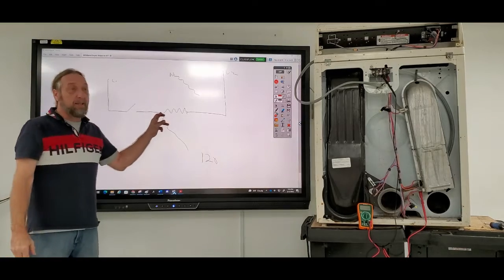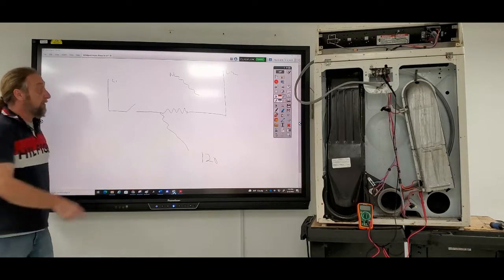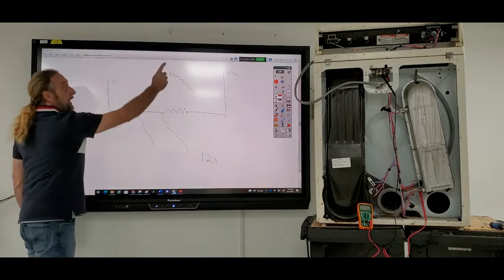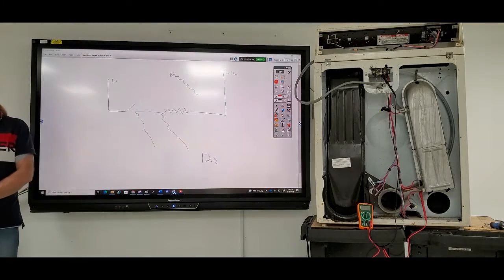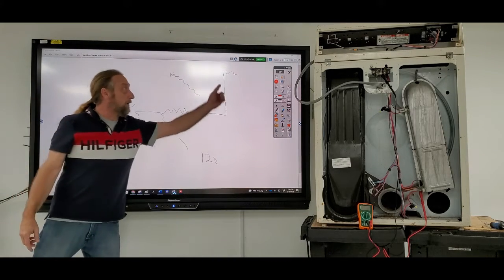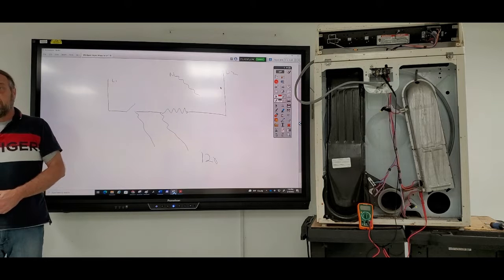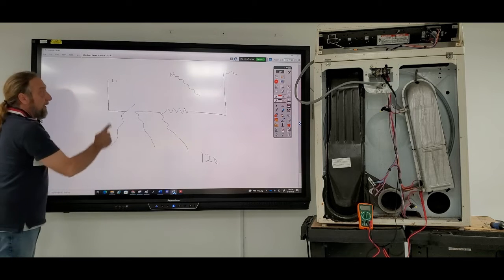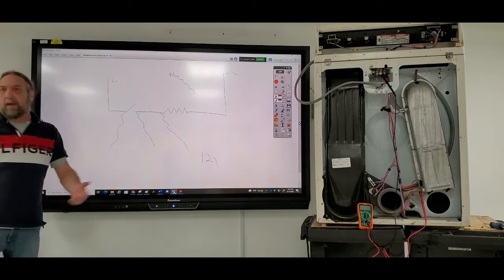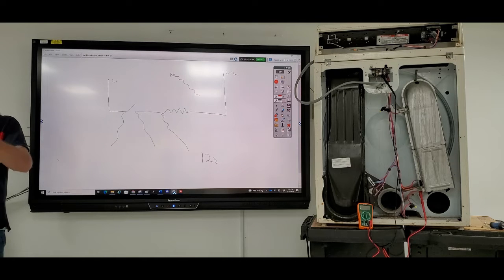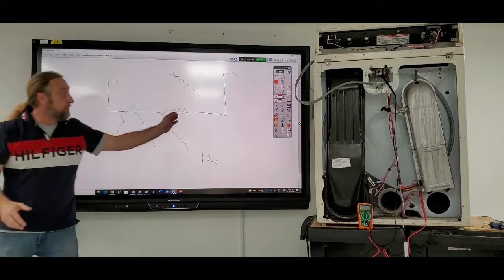So if I went to the other side of the heater, I'm going to have full voltage. If I move this meter lead here to neutral, I have 120, feeding back through the heater. If I move the meter lead here, now I'm on line 1 and neutral, what do I get? 120. So you cannot check a 240 volt circuit this way.